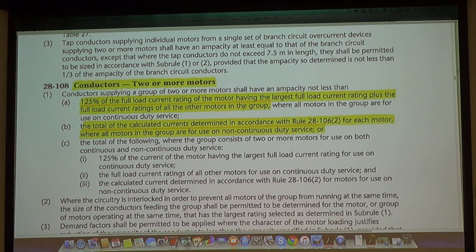So if I was given 10 motors, FLAs was 10 amps, 20 amps, 30 amps, all the way to 100 amps. I will just choose 100 amps times 1.25 plus the rest.